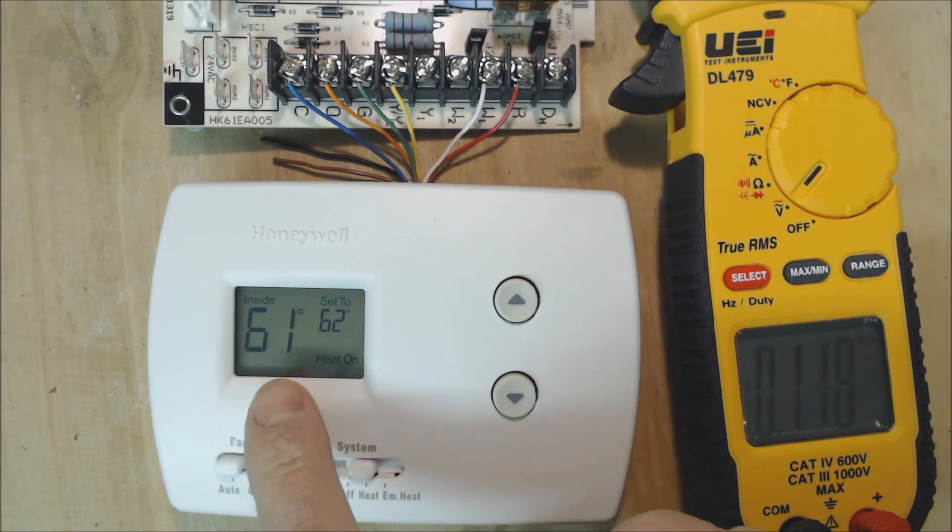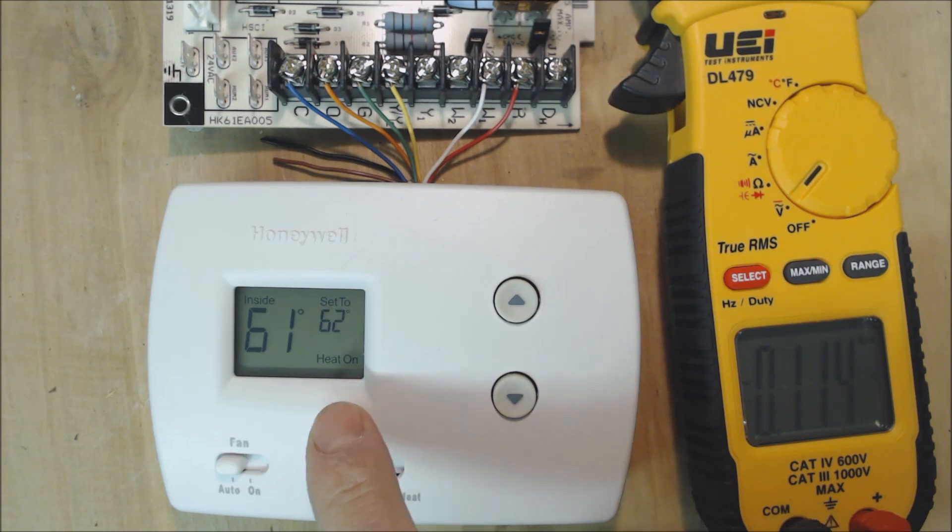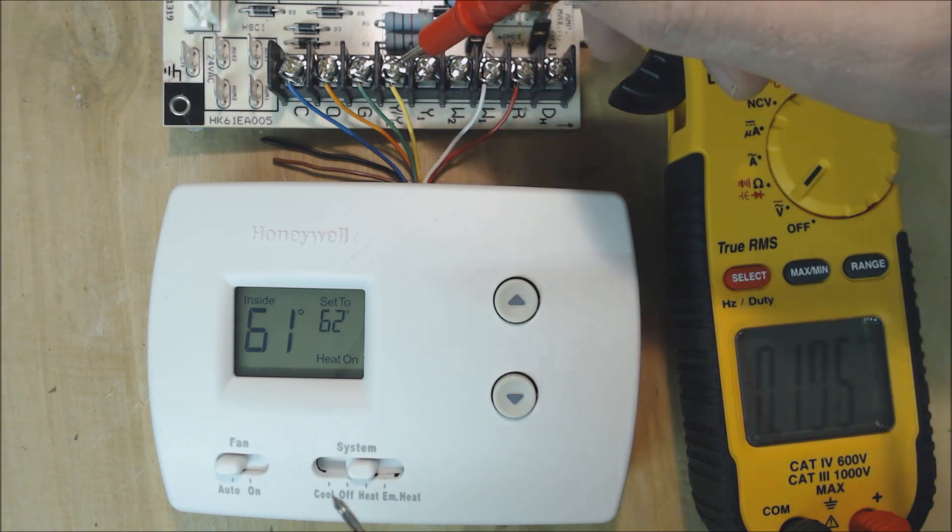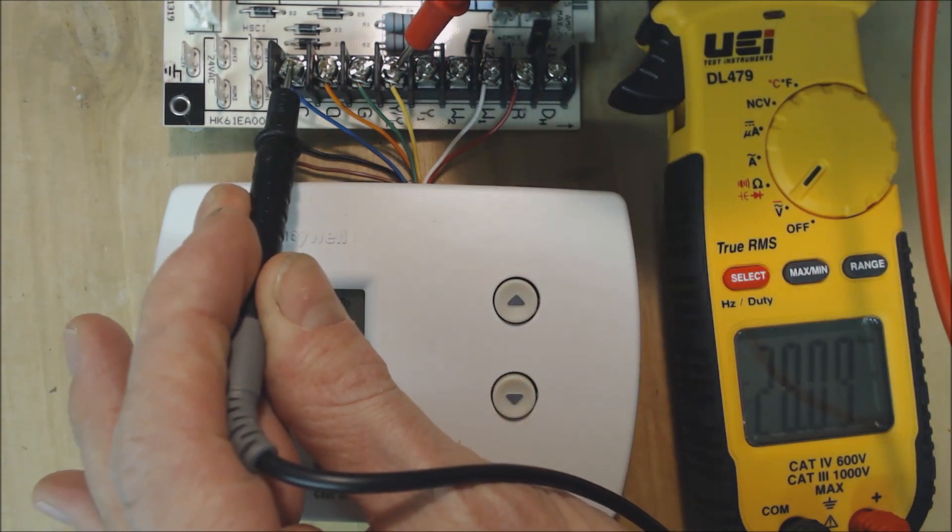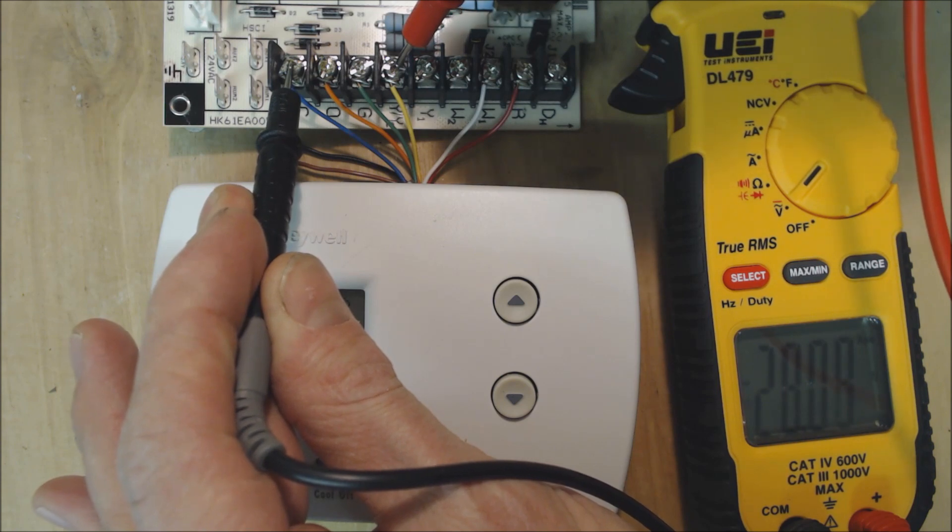The temperature in the room went up to 61. I set it to 62. Five minutes has now passed. Heat is on. R is now touching Y, and we can confirm that by reading right here from Y to C, and we see we're reading 28 volts.